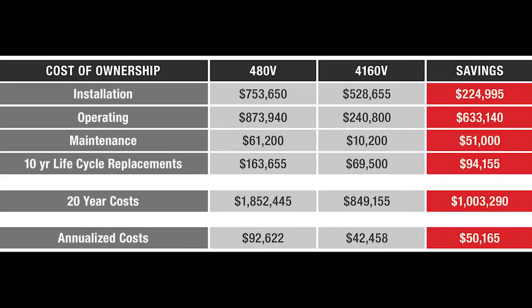At the end of the day, when you add it all up in this real case study for a real customer, what you tend to see is significant savings. These heaters, when manufactured correctly, will run 10, 20 years plus, and over the life of the product you're seeing $1 million in savings. And this is just a 2.5 megawatt system—a reasonable, simple case study, not even talking about the kind of savings over much larger systems.